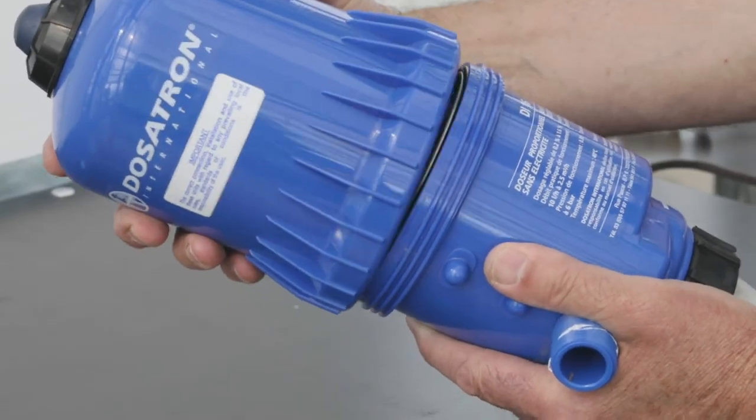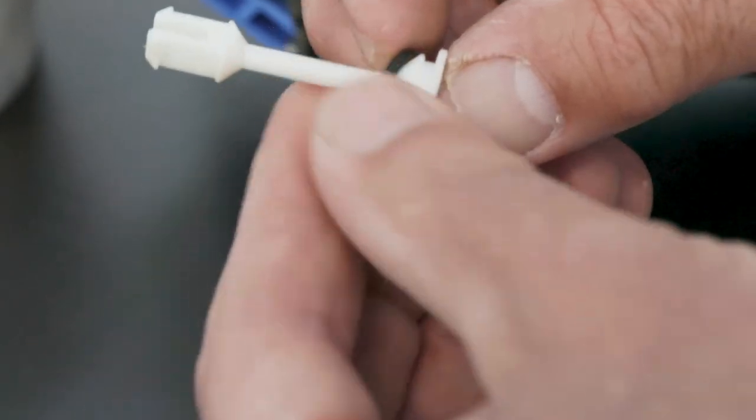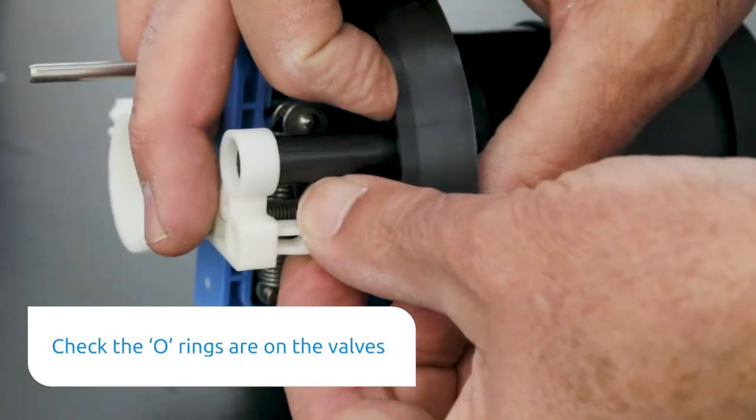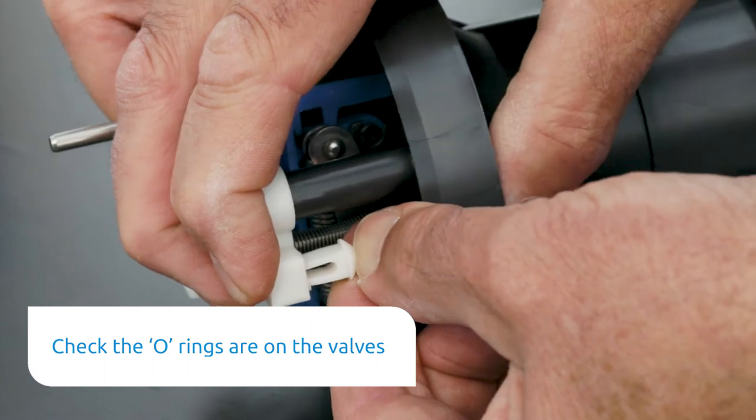Second point is to remember to take them apart every so often and just check to make sure that the o-rings are in situ on the valves.